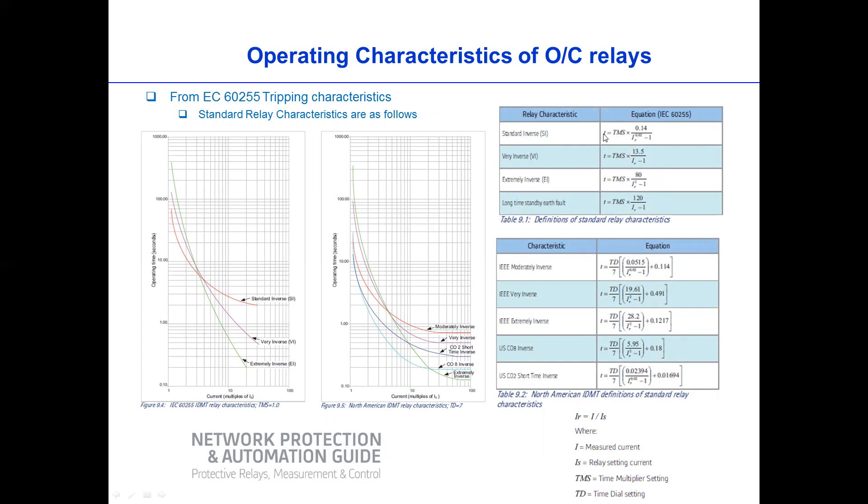And then these parameters are just an explanation to the parameter defined in the equation. So for example, T is time of the relay, TMS is time multiplier setting, and IR is I divided by IS, where I is the measured current during the fault, and IS is setting current or relay setting current.